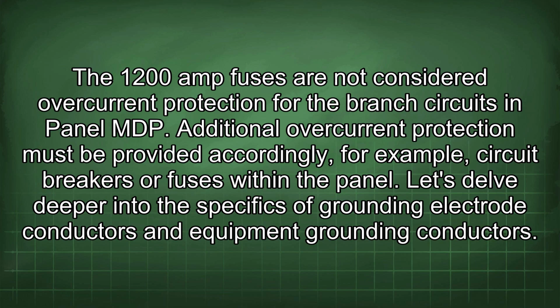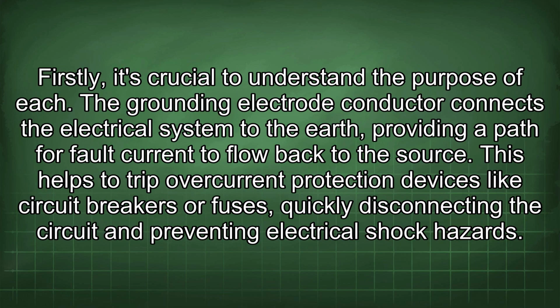Let's delve deeper into the specifics of grounding electrode conductors and equipment grounding conductors. Firstly, it's crucial to understand the purpose of each. The grounding electrode conductor connects the electrical system to the earth, providing a path for fault current to flow back to the source. This helps to trip overcurrent protection devices like circuit breakers or fuses, quickly disconnecting the circuit and preventing electrical shock hazards.